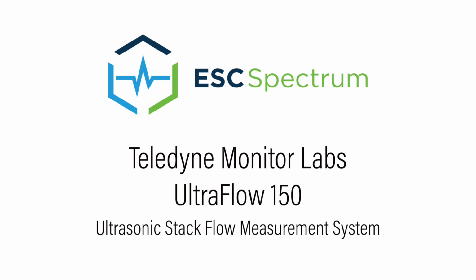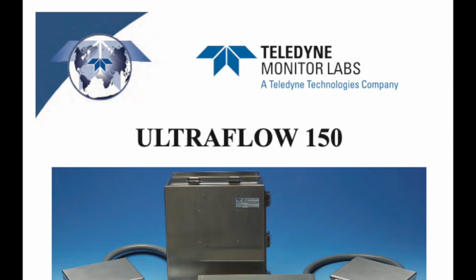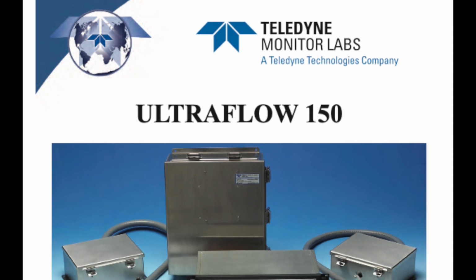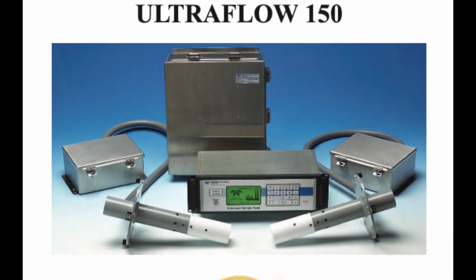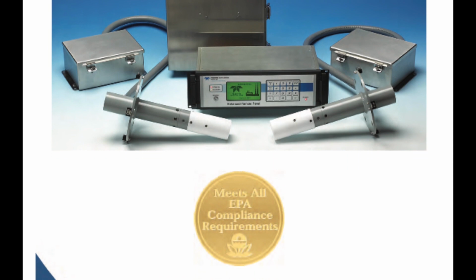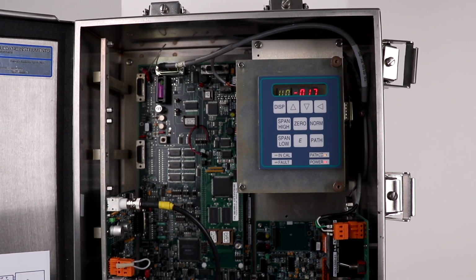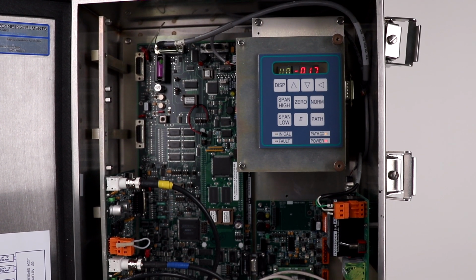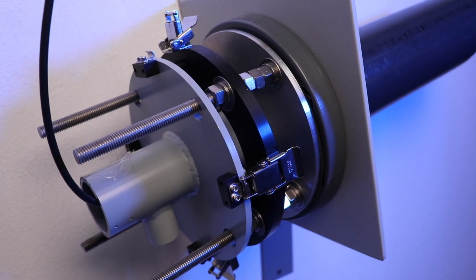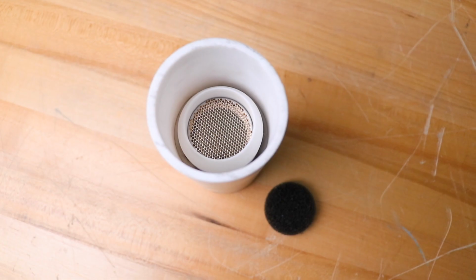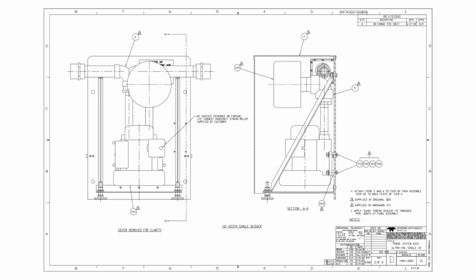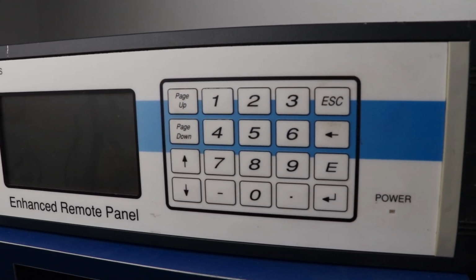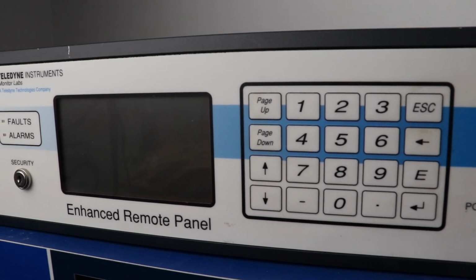In this video, we will discuss the operation and major components of the Teledyne Monitor Labs UltraFlow 150, the ultrasonic stack flow measurement system. The standard UF-150 system consists of the following pieces of equipment: Transducer Interface enclosure, or tie box, purge nozzle assembly, transducer, protective purge air system, and the enhanced remote panel, or ERP.